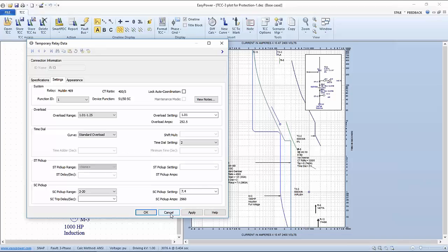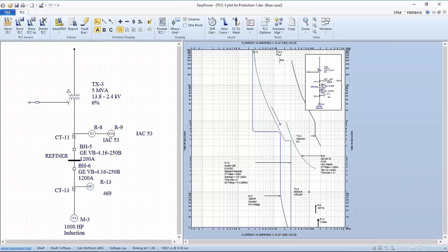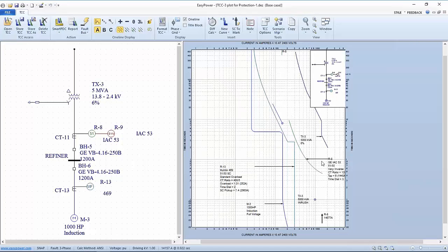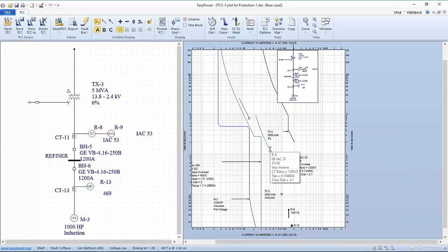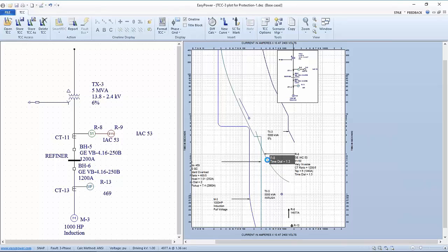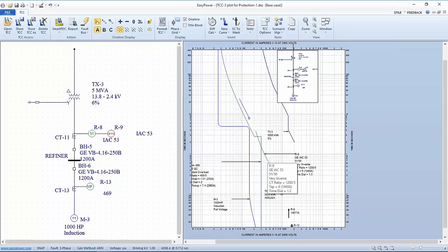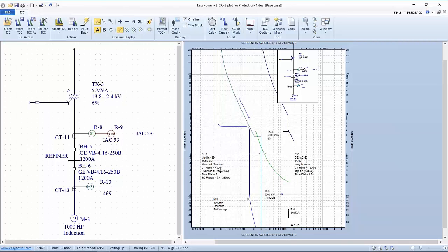This performance curve is a function of how we set the settings on, and in the case of collecting data, how we recorded the dial settings, both for the overload and the time delays for this particular relay. That's why it's important when we're doing data collection to make sure we record each one of these elements because they may have a different format based upon the way the manufacturer presents the information. They could be physical dials. They could be digital settings. They could be switches, DIP switches that we need to read or verify what the settings are. Each of these settings will affect where the plot or the performance of that curve.